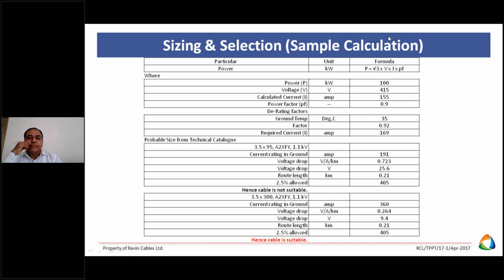Sir, in the upper slide, you are given power factor will be around 0.9. Suppose it may come to 0.89 or 0.90 or 0.91, depending upon the capacitor weakness. Whether it will affect the load or what, sir? Definitely it will affect, but only minorly, because we are taking so much into consideration for derating. Around 30% derating factors are considered for cables. So it hardly matters, 1.5%. Okay, so it does not affect much. This is a minor effect, no, sir.